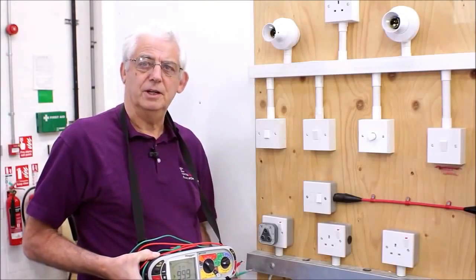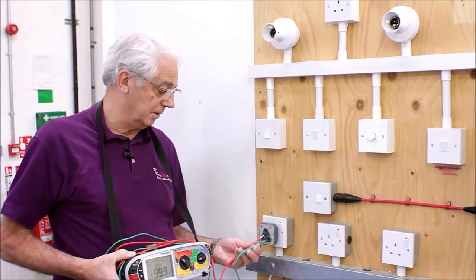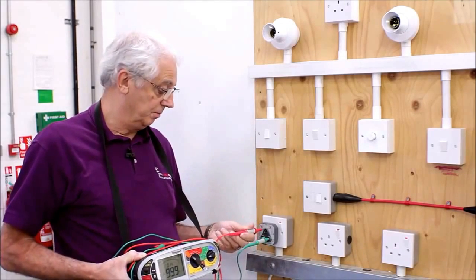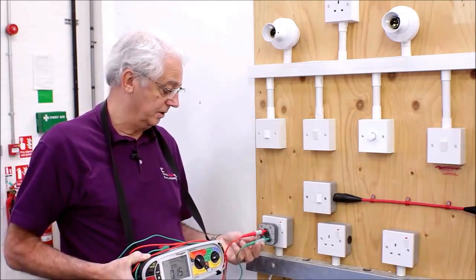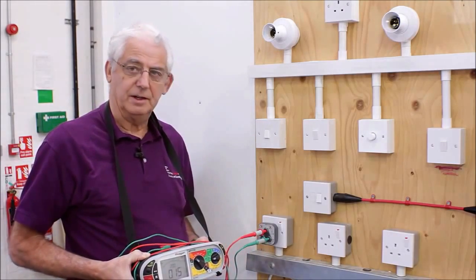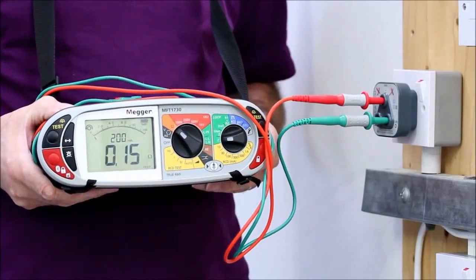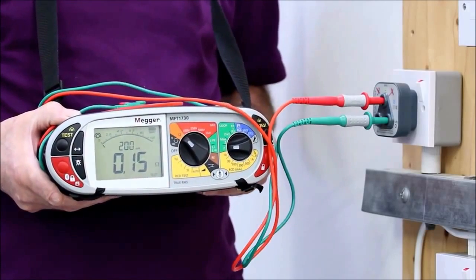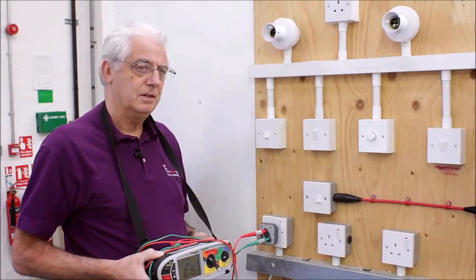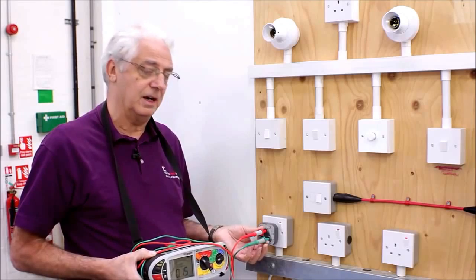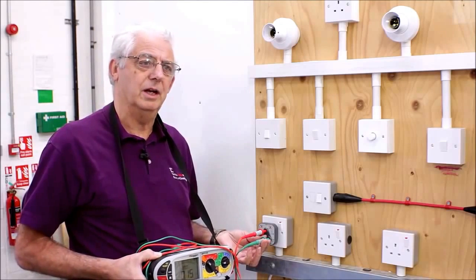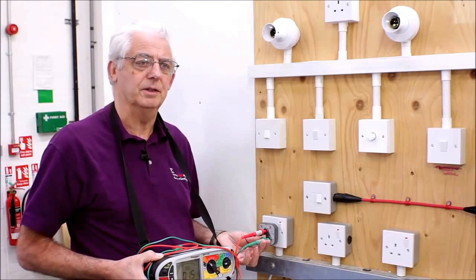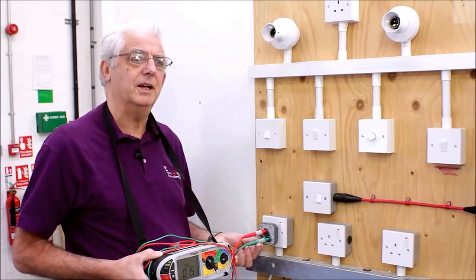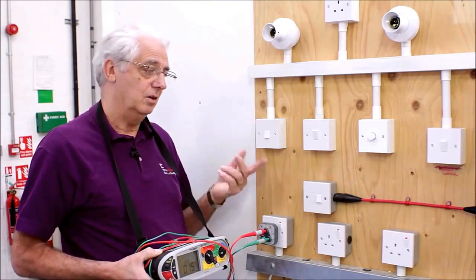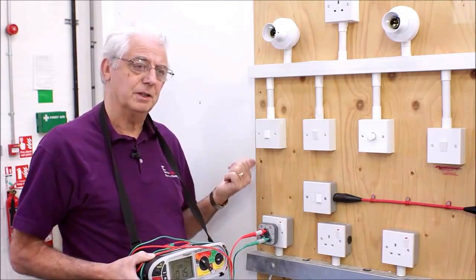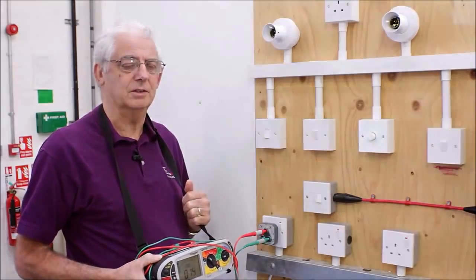I'm now at the last socket, I'm just carrying out the final test. Up till now, they've all been within 0.05 of the original value. Take the reading again, and again, perfect reading. That tells me that all of these sockets are on the ring. The highest of these values which I've taken, I'd record down as my R1 and R2 value for the ring. But of course, my job's not finished yet because I still need to use line to neutral connections to make sure that the polarity of the ring is correct.